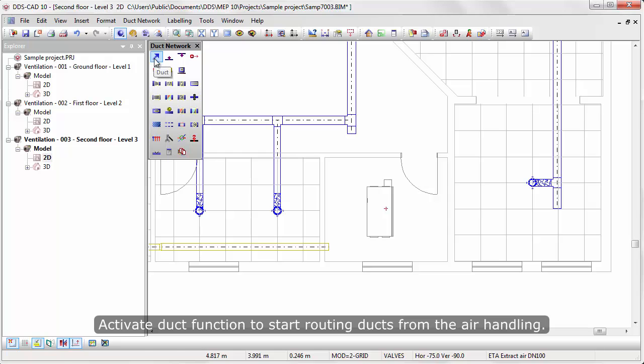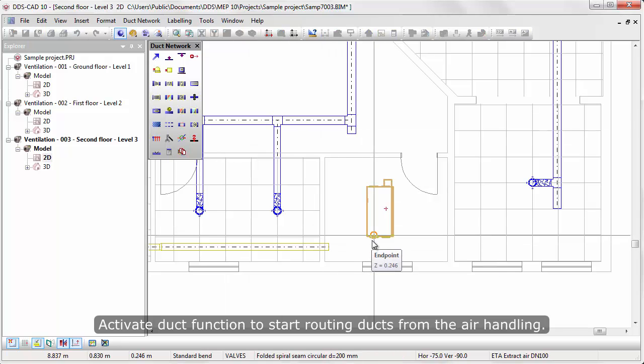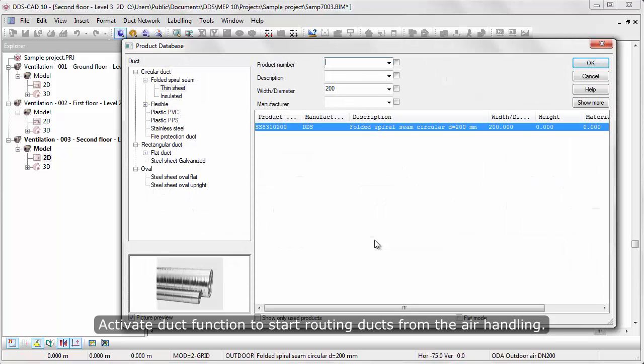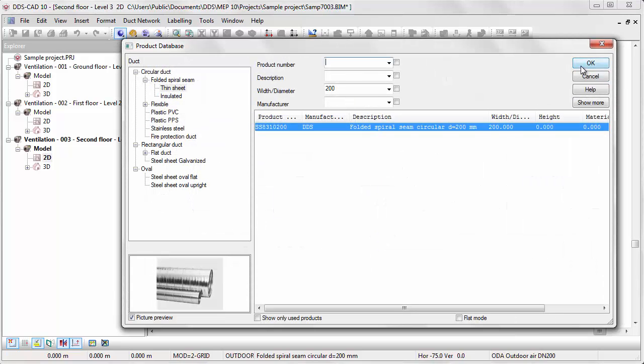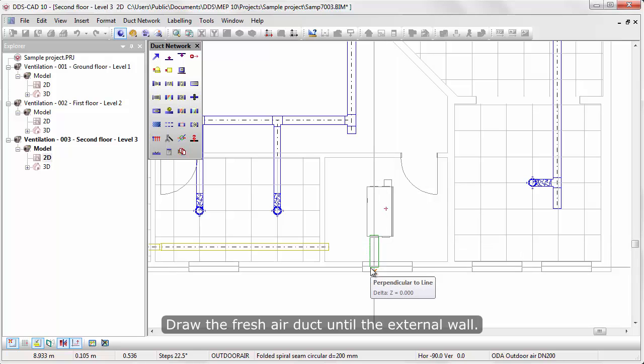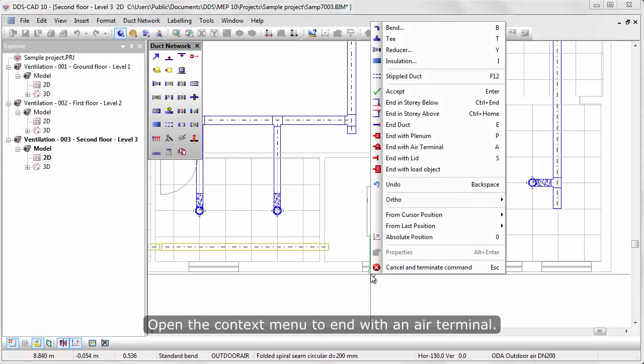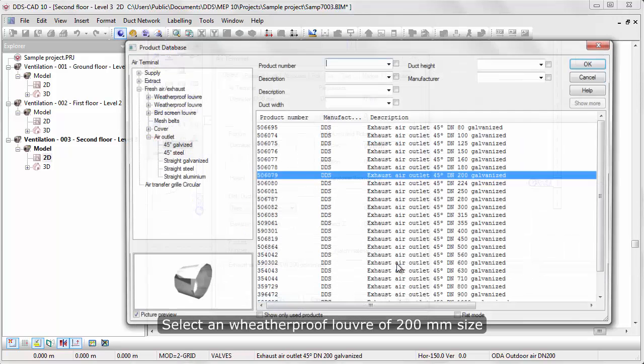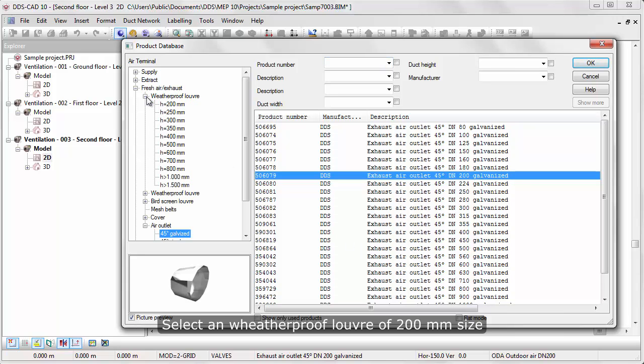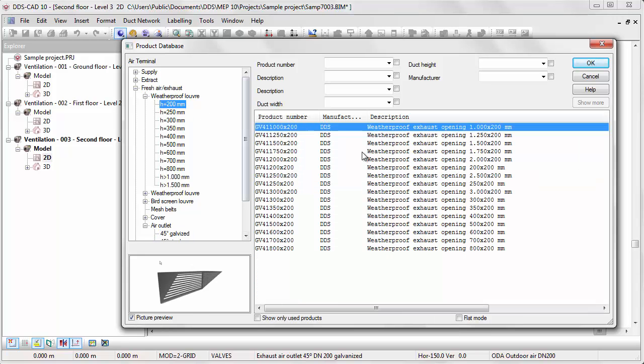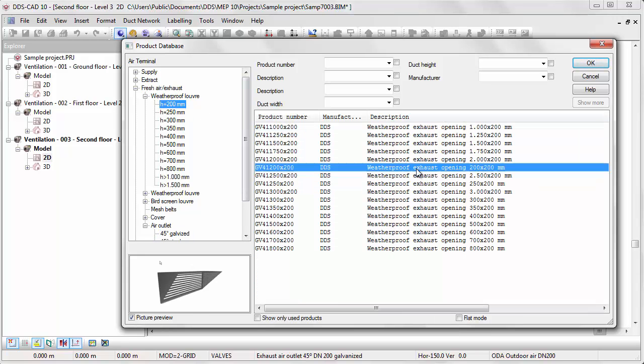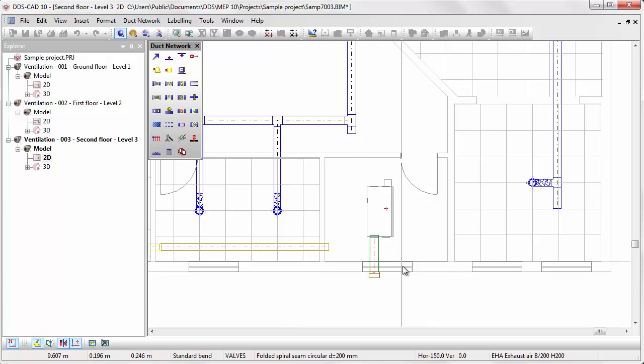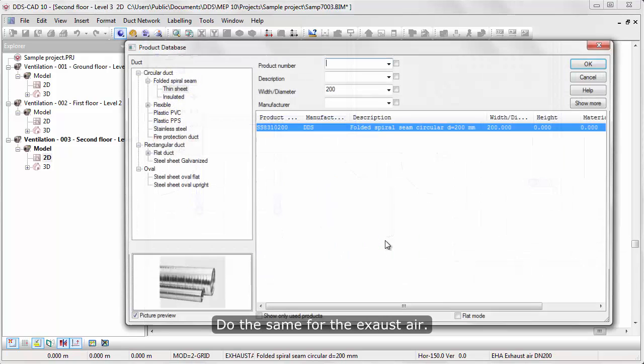Activate duct function to start routing ducts from the air handling unit. Draw the fresh air duct until the external wall. Open the context menu to end with an air terminal. Select a weatherproof louvre of 200 mm size.